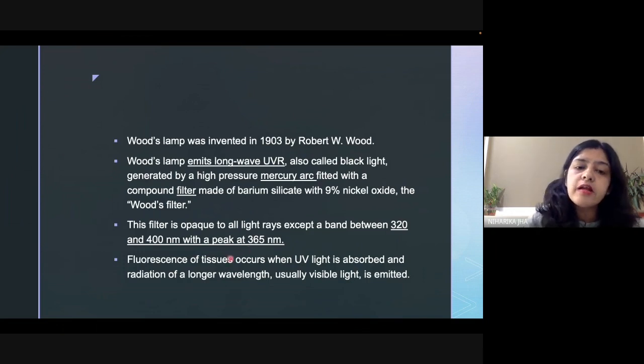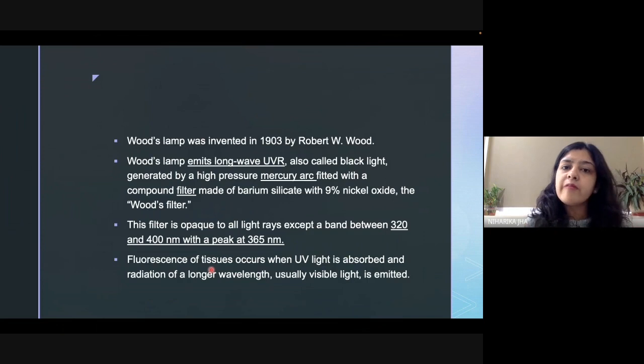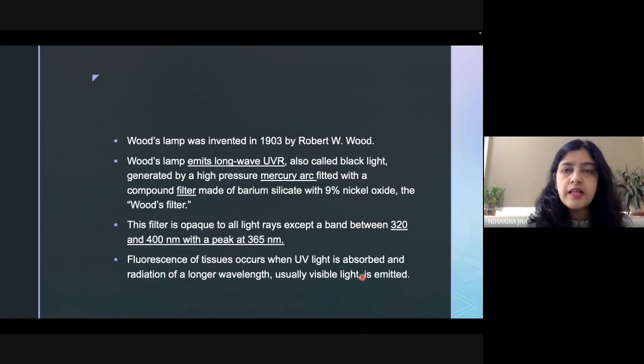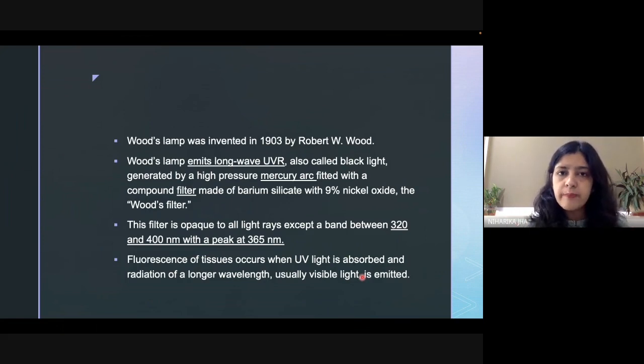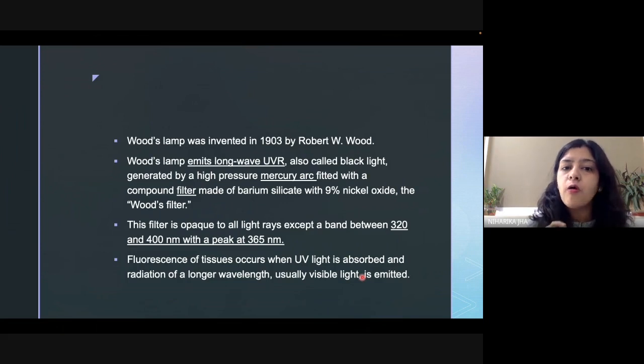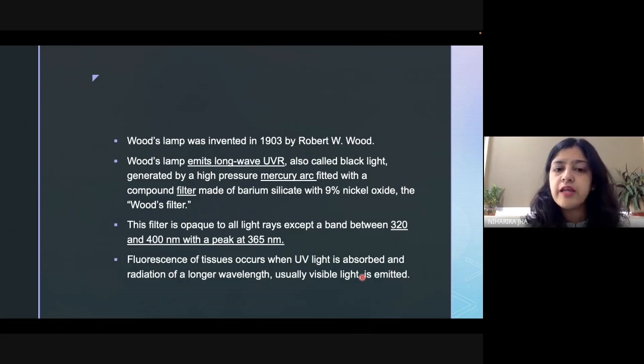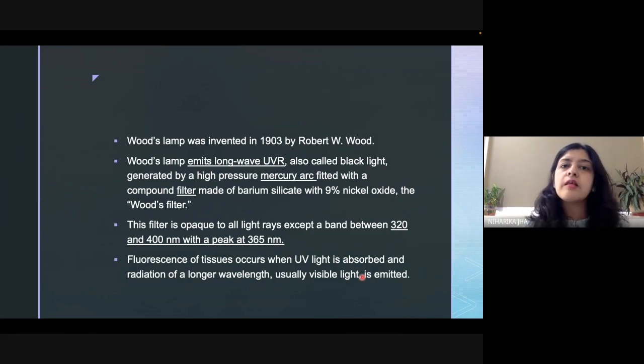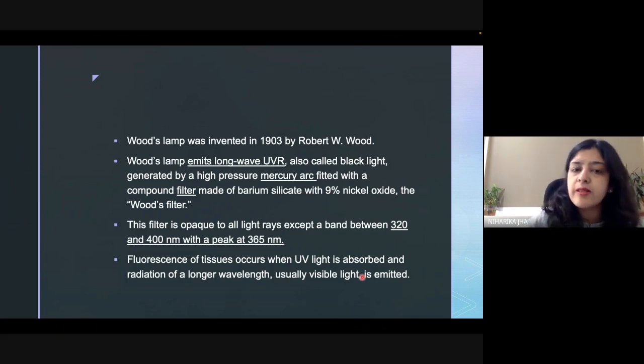How is this fluorescence created? When the tissue absorbs this particular UV radiation and in return emits a radiation of a longer wavelength — usually visible light — we see it as fluorescence. So basically, the mercury arc emits long-wavelength UV radiation; the filter allows only those light rays between 320 to 400 nanometers, which is absorbed by the tissue, and then it further emits radiation as visible light.